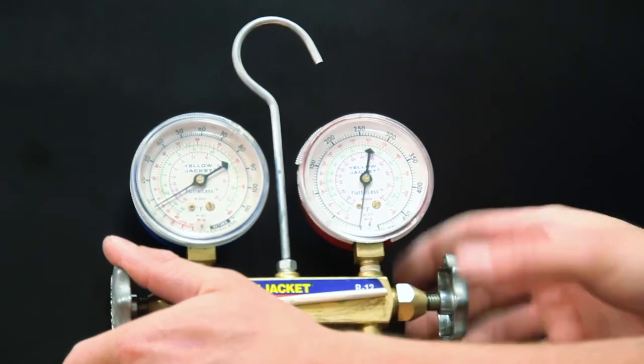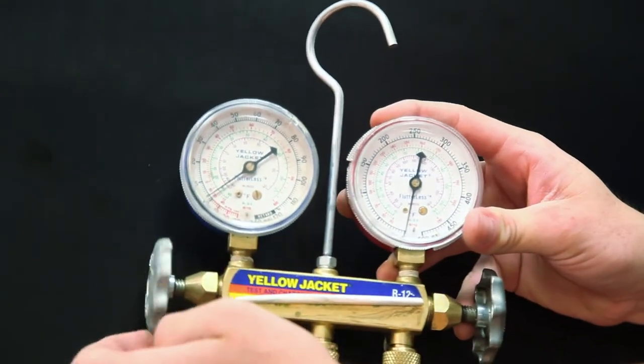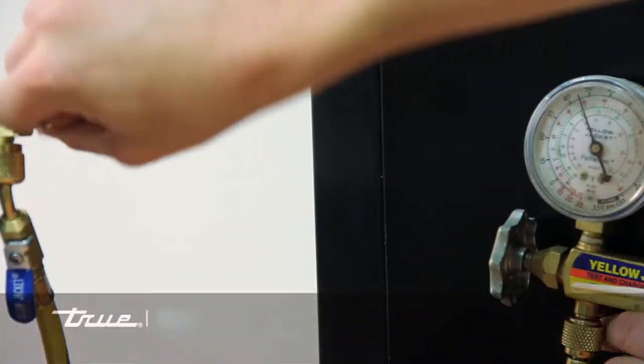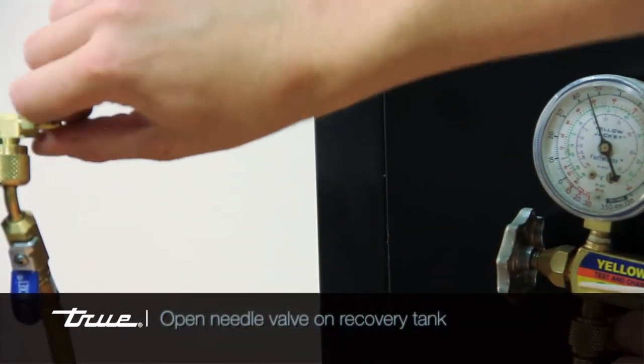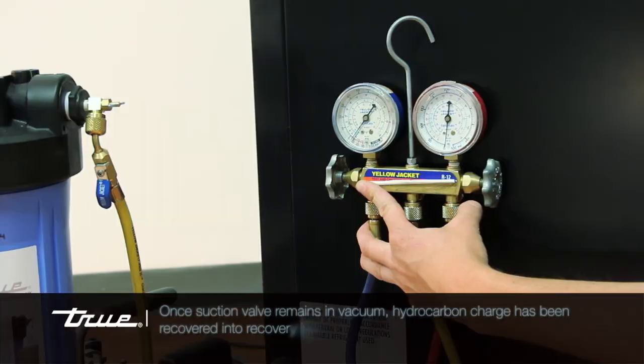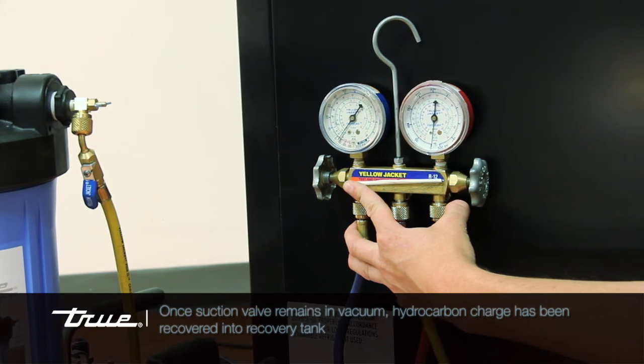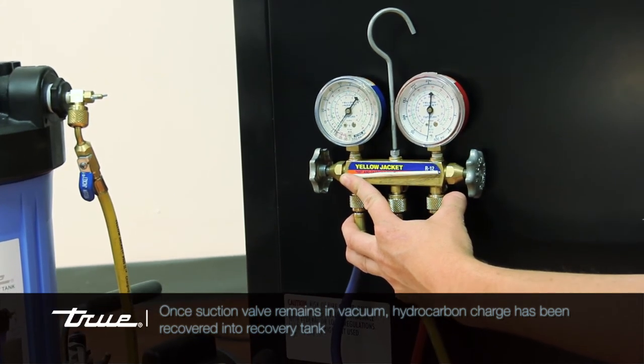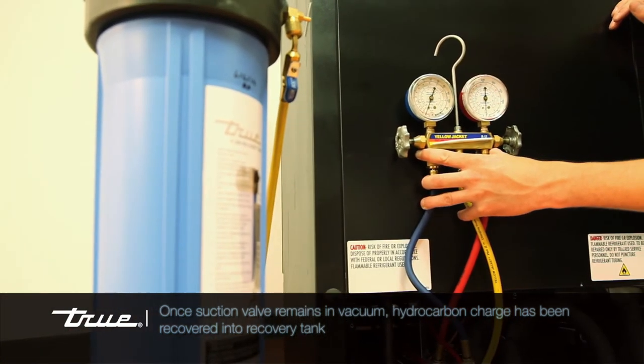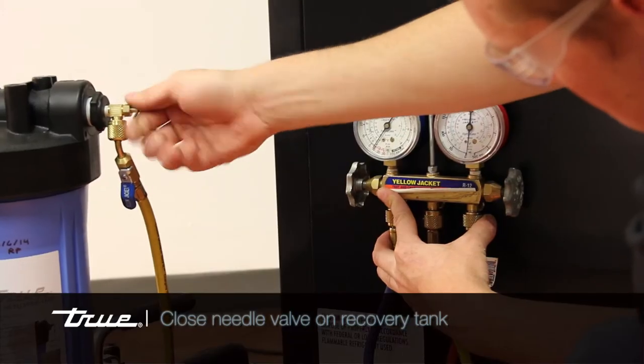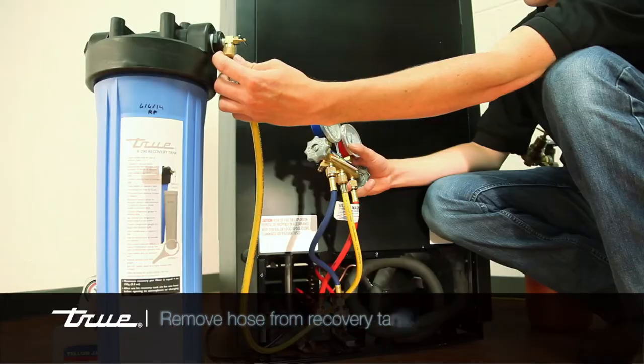Open your refrigeration gauge ports and then open the recovery tank needle valve to allow the refrigerant in the cabinet to be absorbed into the tank filter. Once the suction valve remains in vacuum, hydrocarbon charge has been recovered into the recovery tank. Close the needle valve on the recovery tank and remove the hose from the recovery tank.